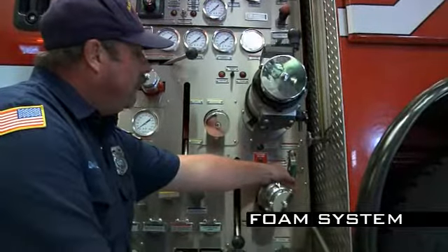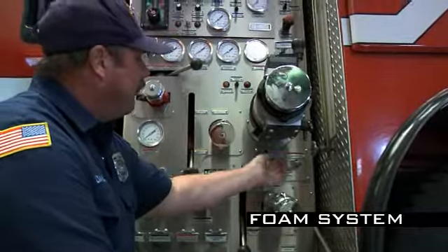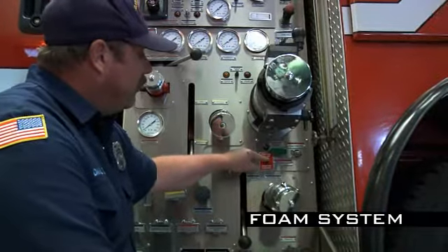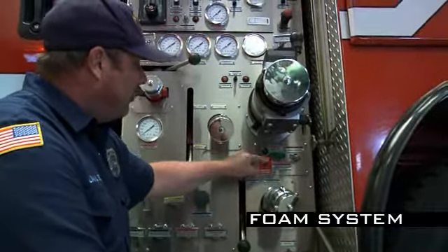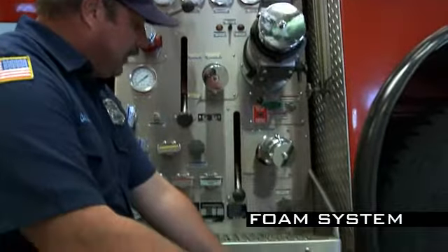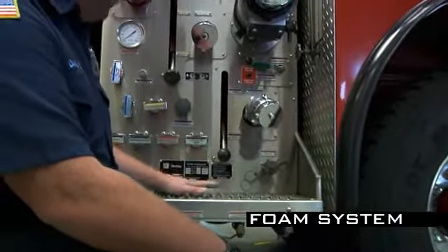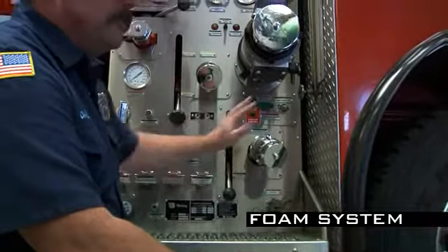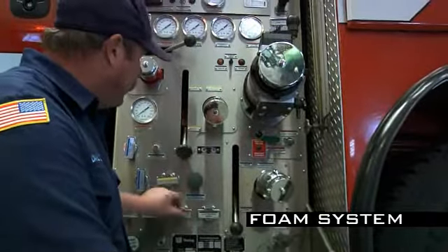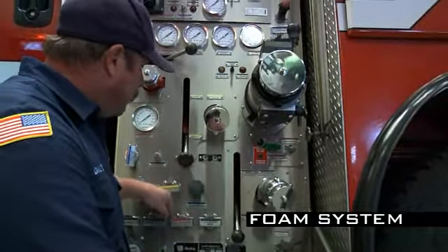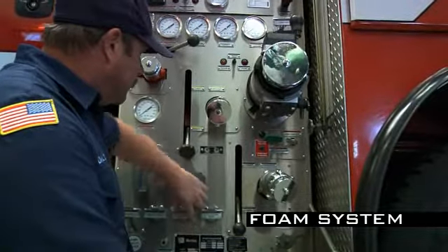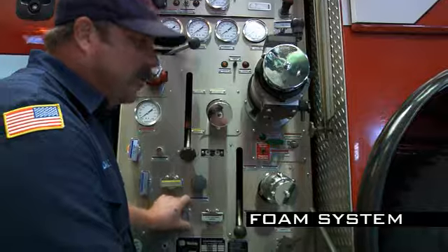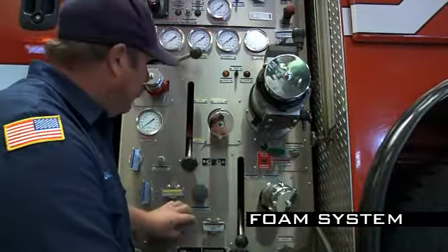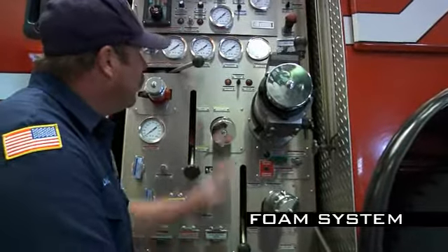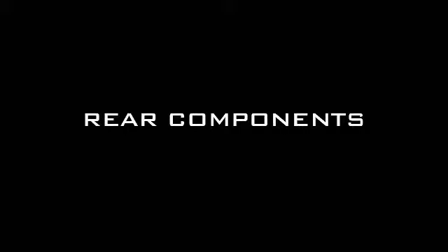Okay. After you've done that, you want to go ahead and move it over to flush and push this down to activate the motor to flush the system. You should see some items coming out here. After you've utilized all of your foam system, you've refilled it, and you've reset the presettings where you need to, make sure that you turn on your foam line pressure release, or activate it, to release the pressure out of the system before you leave the rig, because it'll tend to hold pressure within the system and cause some damage.